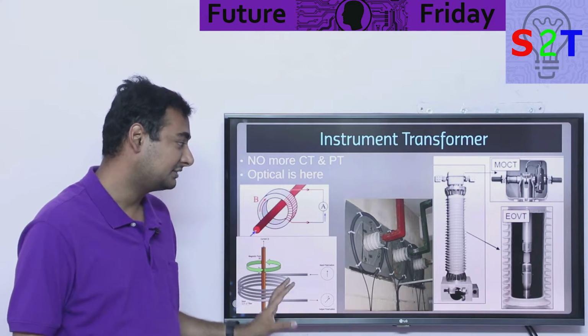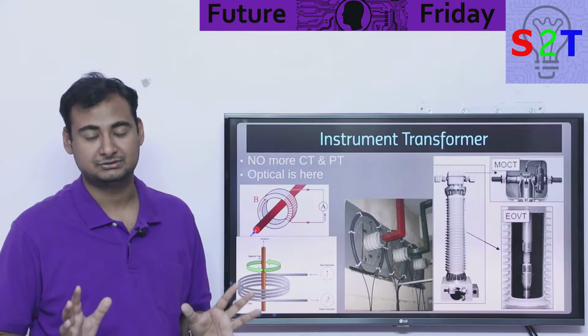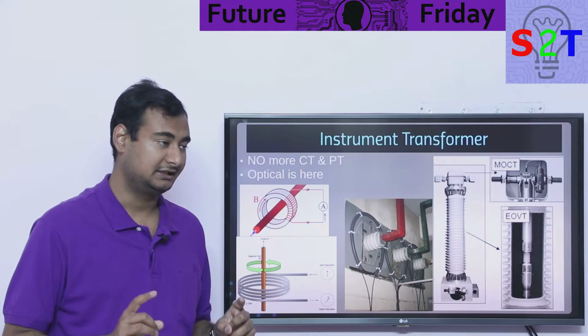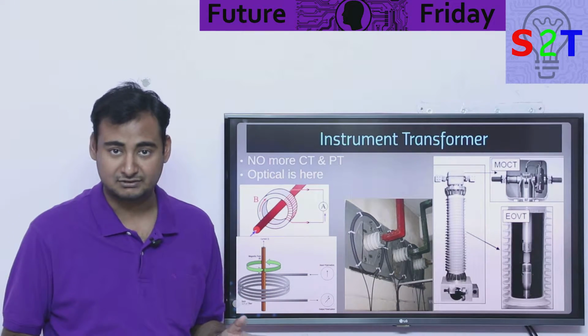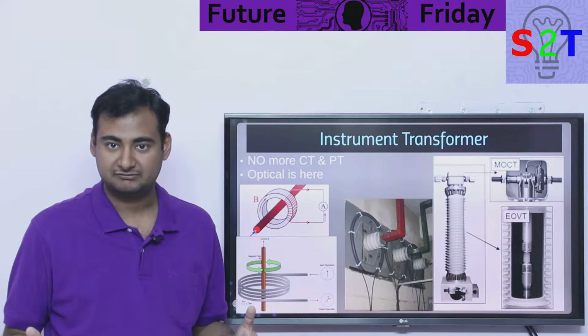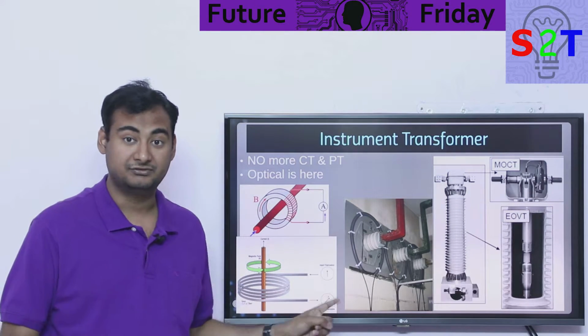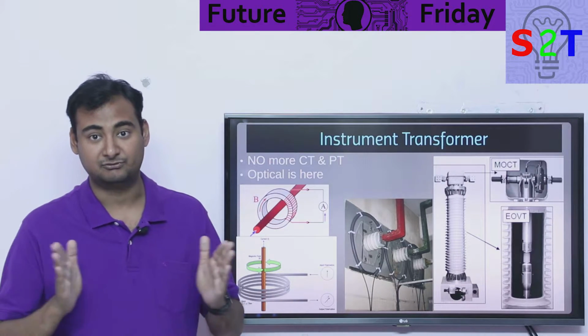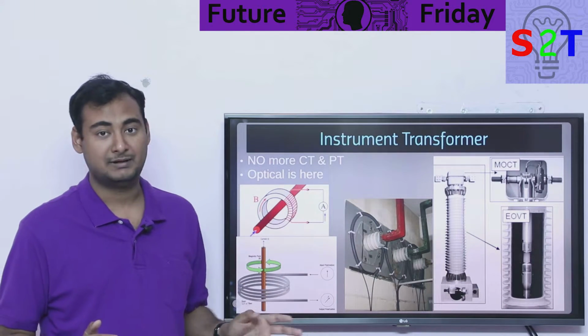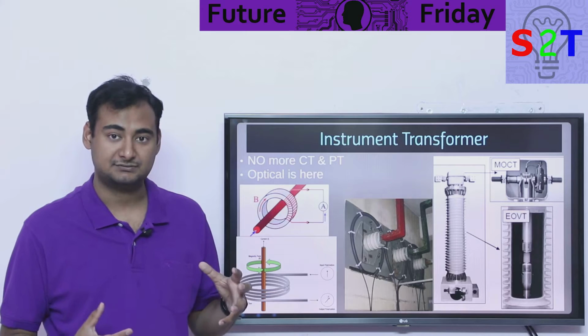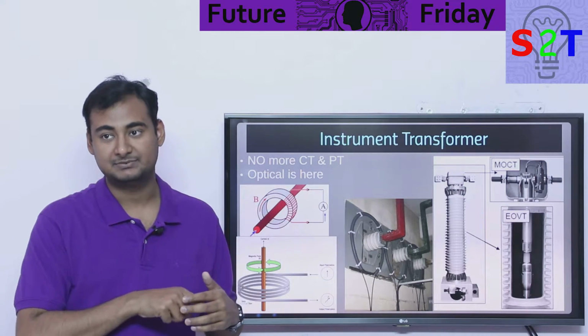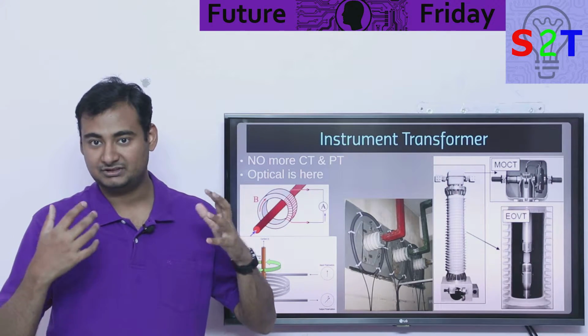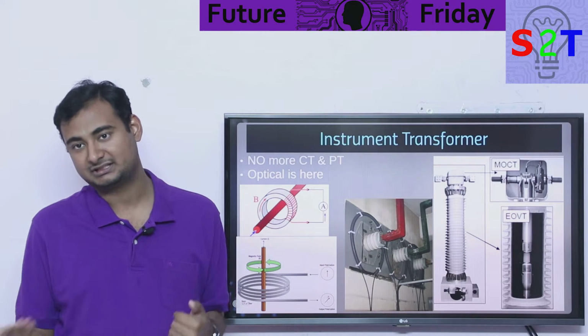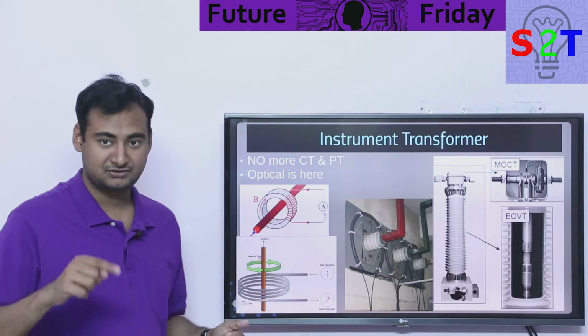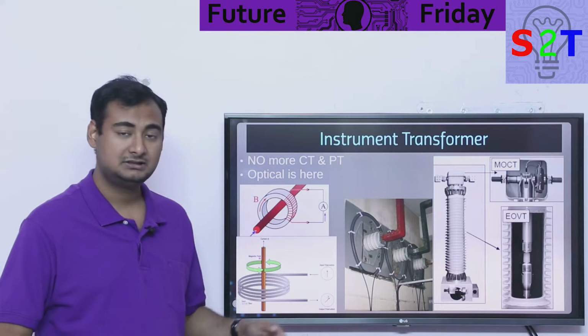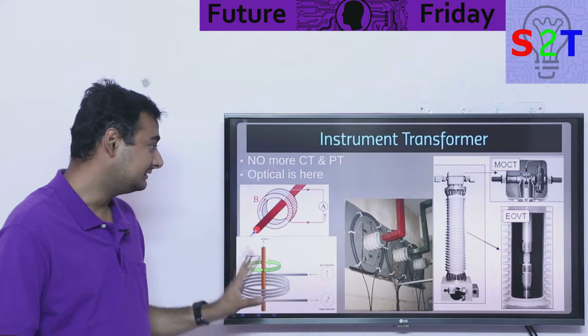That's how we can measure very high amounts of current without suffering the consequences of having a transformer that blows up when it faults out. These are very fast, able to measure in like 1/100th of a second, and there's no magnetic saturation. With transformers, if a spike happens you can't detect it because the transformer takes time to absorb the magnetic flux, so it can't do high resolution in terms of measurements per second. Optical can handle it. So this is how we're gonna do it.